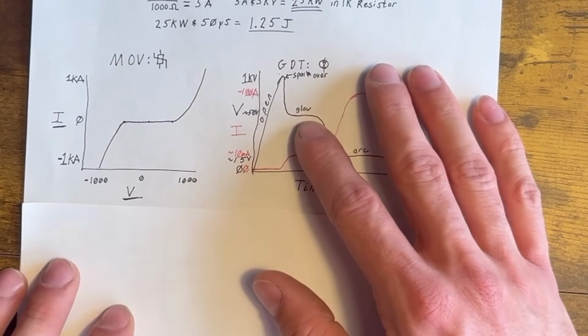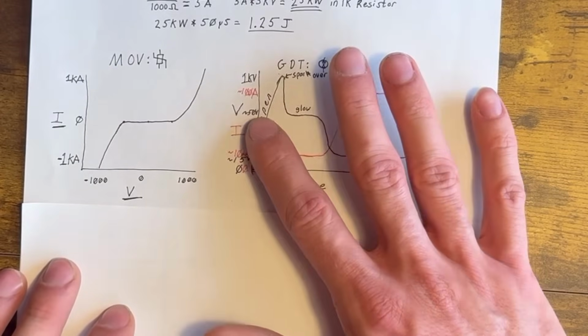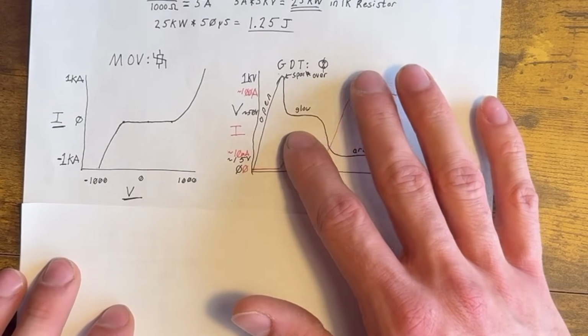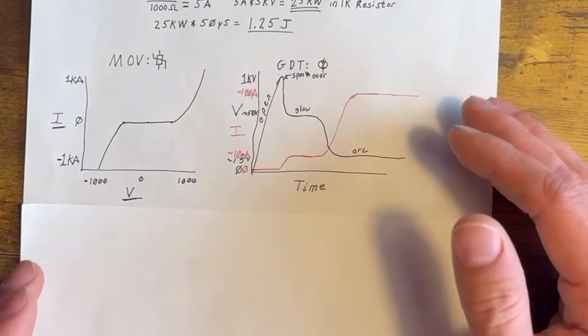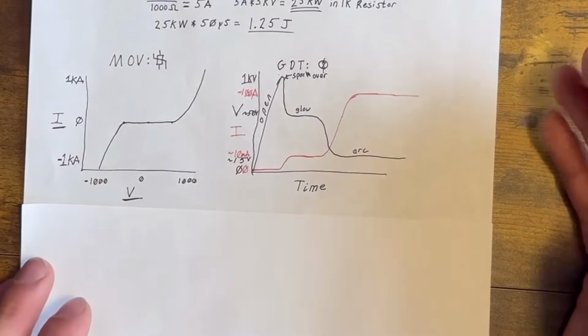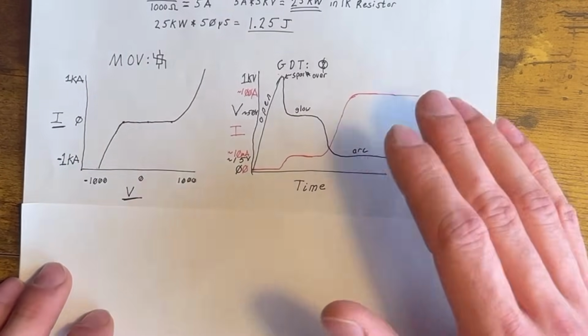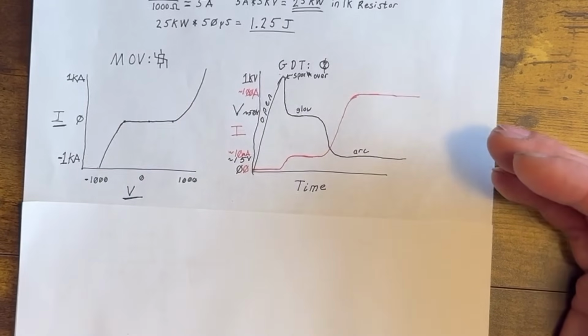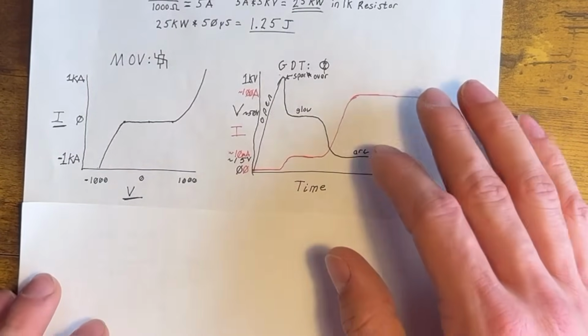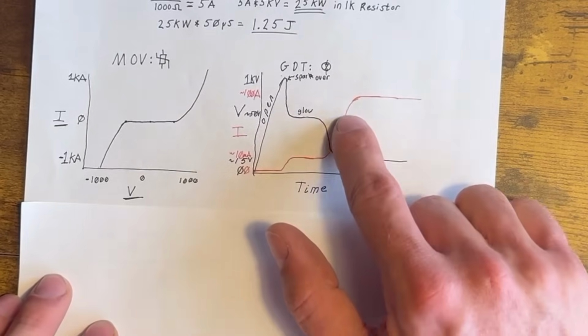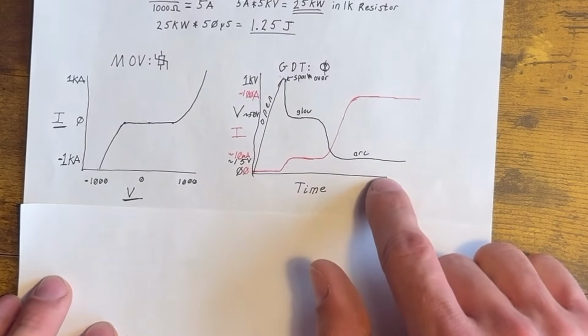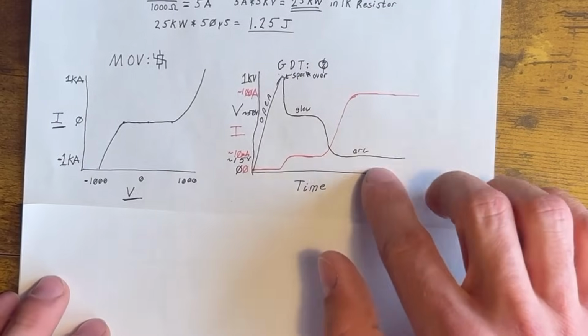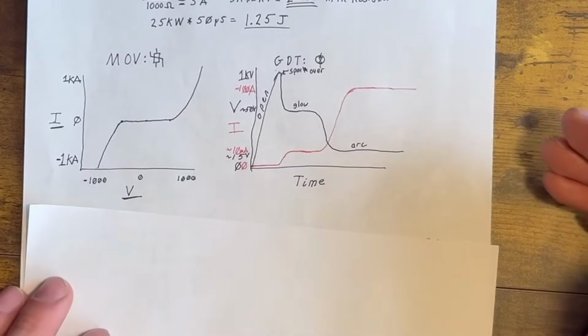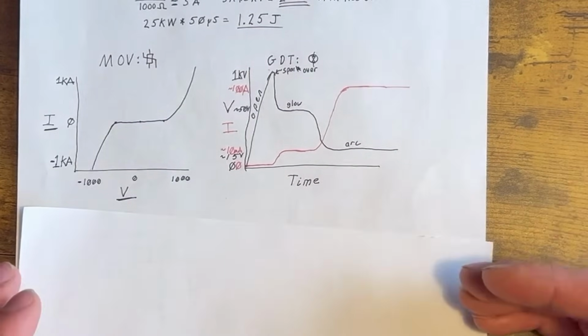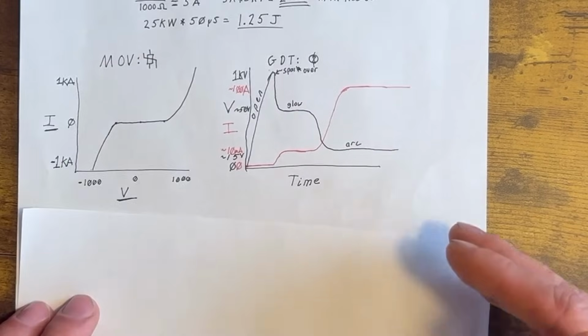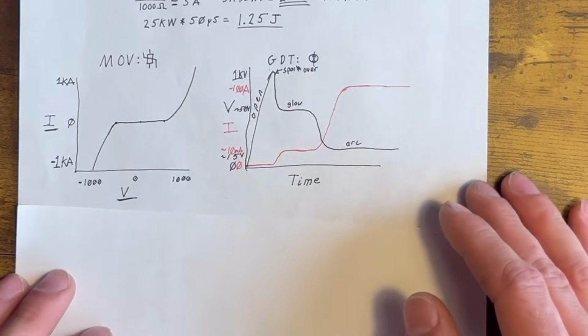If the source impedance is very high, enough so that the voltage drops below maybe 50 or 60 volts, under a 10-ish milliamp load, then the GDT can stay here or even extinguish, go back to non-conducting. If the impedance is a little lower though, the voltage source can supply significant current, then the arc strikes and the GDT becomes something close to a short circuit, passing a very high current with very little voltage drop. Even though the voltage across the GDT is low at this point, this condition will persist as long as current is supplied. It's only once the supply shuts off, or the transient ends, and we stop pushing current through the GDT that it returns to high impedance.